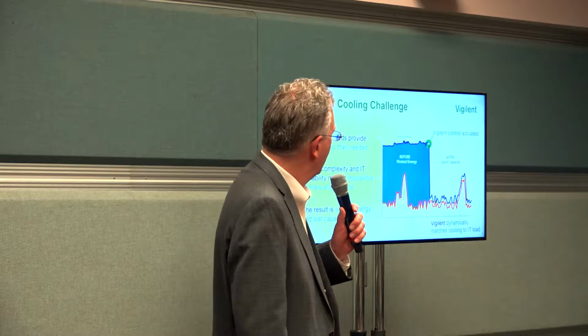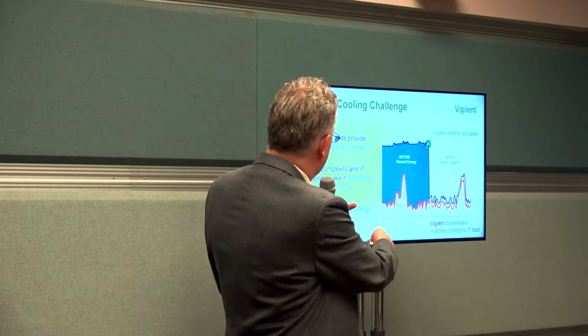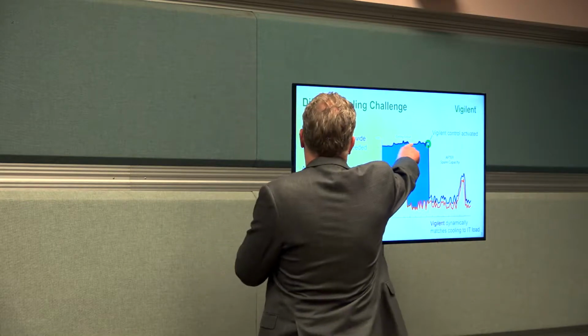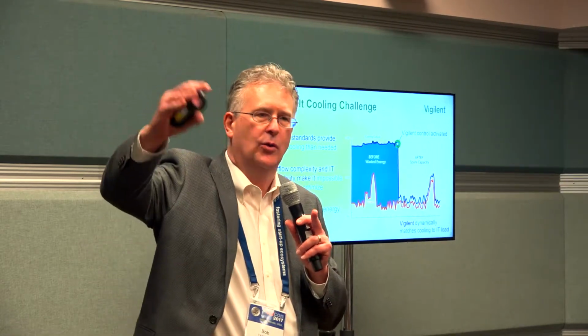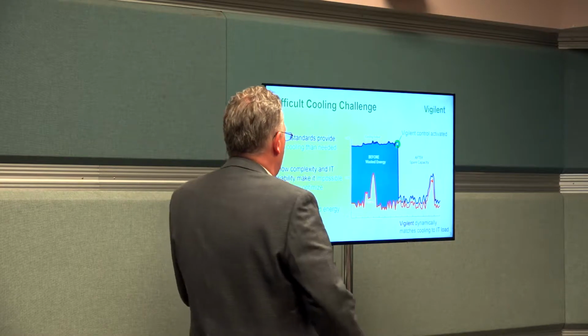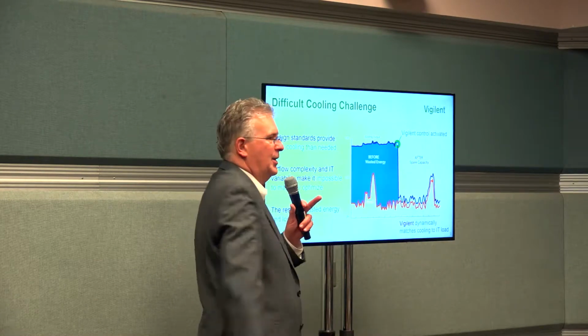It's a very difficult problem to solve actually, you wouldn't think it'd be that difficult, but it is. The way these things are typically designed is people size the amount of cooling, all the air conditioners, for the hottest day of the year at peak load. So it's up there at the very top, and most people leave it there. There are sometimes simple controls or manual adjustments, but the cooling doesn't vary much, while the IT load may be varying down here. So what you end up with, shown in blue, is a huge amount of wasted energy.